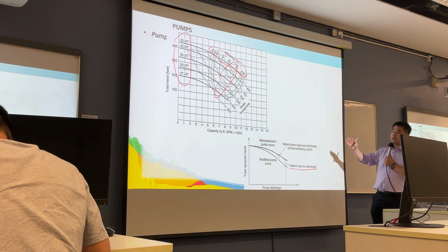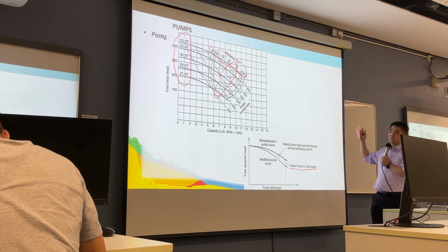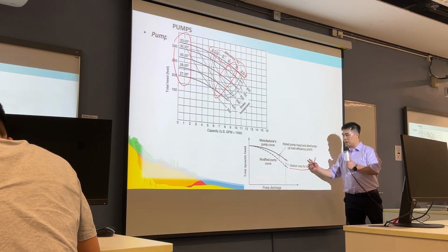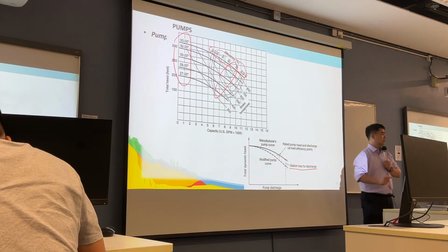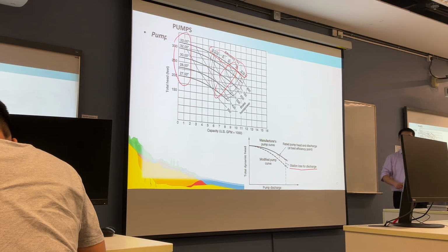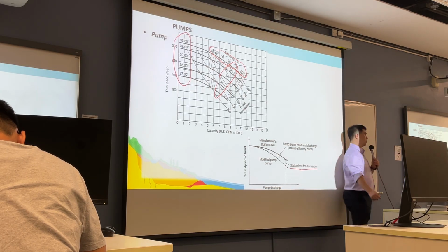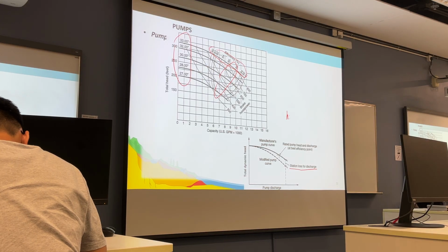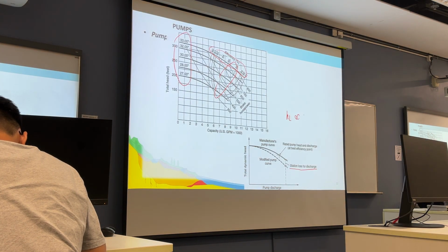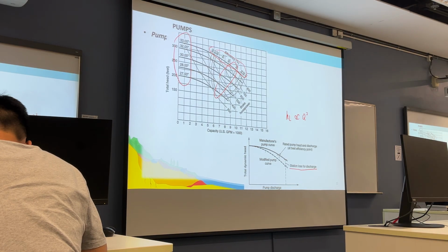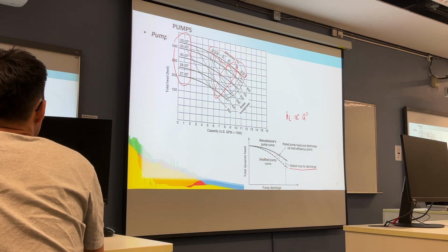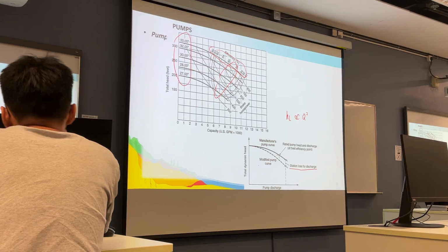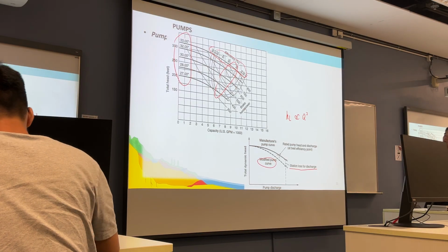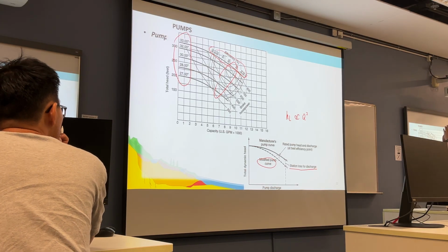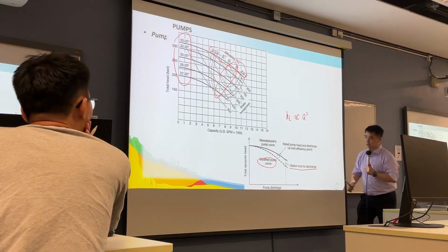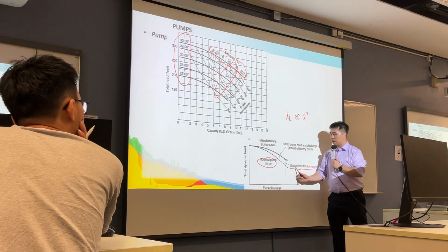Outside of the pumping station is the head loss due to the water supply system. So this counts the loss from the pumping station. Now the head loss is usually proportional to the power 2 of the discharge. The head loss is proportional to Q squared. So if the discharge is larger, the gap grows. The modified pump curve is the actual performance of the pump after subtracting the head loss from the pumping station.